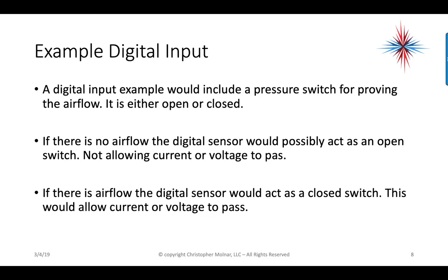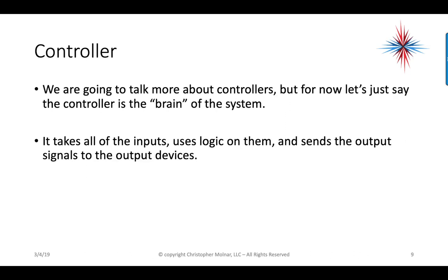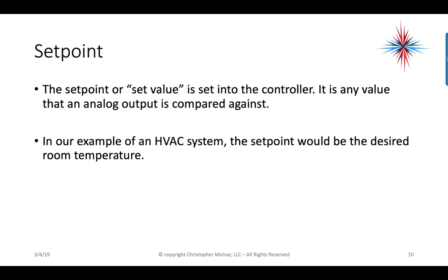It's either on or off, open or closed, true or false, 1 or 0. The controller — we're going to talk much more about controllers — but for now, the controller is the brain of the system. It acts as the computer that uses these inputs, applies logic and programming, and sends output signals to the output devices. There's always a set point — a set value stored in the controller, which is any value used with an analog output to compare against. In an HVAC system, the set point would be the desired room temperature.